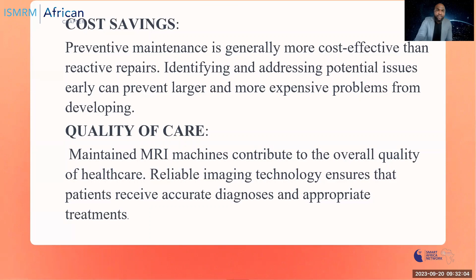Quality of healthcare. Consistent quality of diagnostics, accurate and reliable results. MRI systems must consistently produce high quality diagnostic images. Preventive maintenance includes calibration and performance checks to ensure that the images are accurate, reliable, and consistent. Consistency in image quality is crucial for accurate diagnosis and effective treatment planning. Artifact reduction. Maintenance helps minimize image artifacts, which are unwanted anomalies or distortions in MRI images. Artifacts can hinder accurate diagnosis and may necessitate repeat scans, adding time and cost to patient care. Reducing artifacts through maintenance enhances the efficiency of the MRI system.